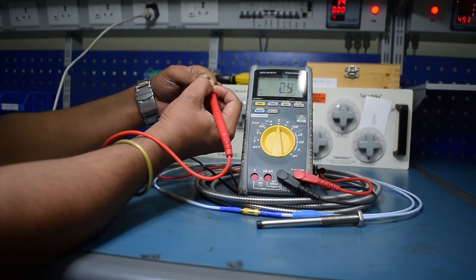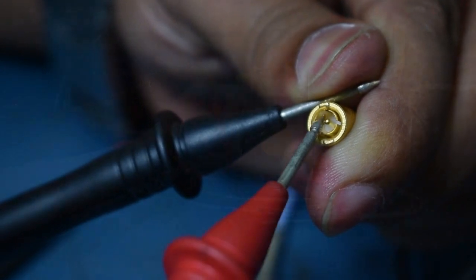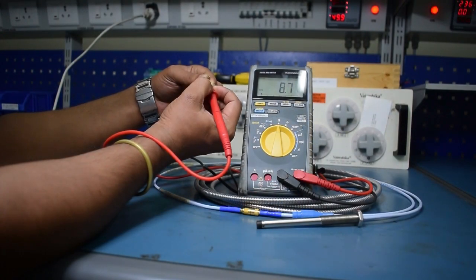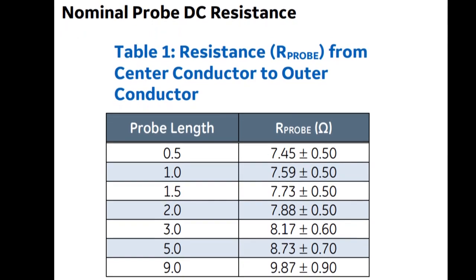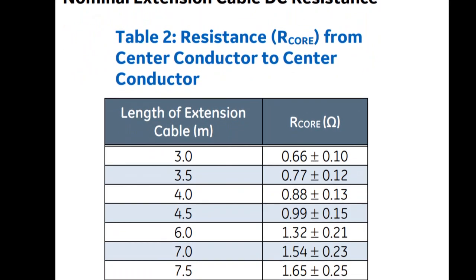The first step for verifying a proximity transducer system is to measure the resistance of the extension cable and probe. The normal resistance should be between 7 and 11 ohms depending on the system length. The datasheet for the transducer system lists the resistance values for the available probe length.